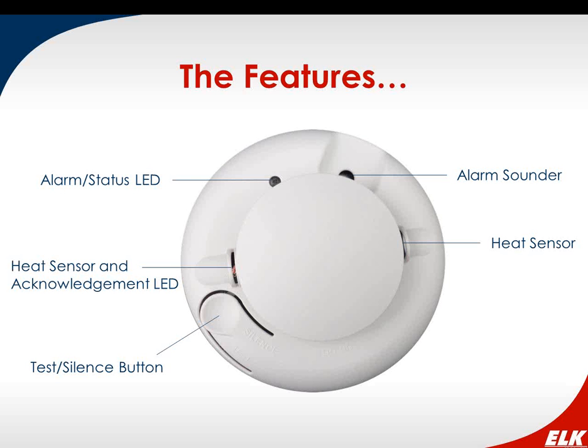When the sensor detects smoke or heat and goes off, that LED is going to come on. So you're going to have an on solid there when there's an alarm. If there's a trouble condition, the LED will go off and you will no longer see your 16-second heartbeat. Now a trouble would be like a low battery, or if the sensor is unable to communicate with the control.